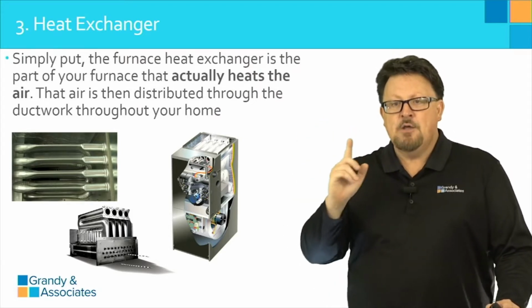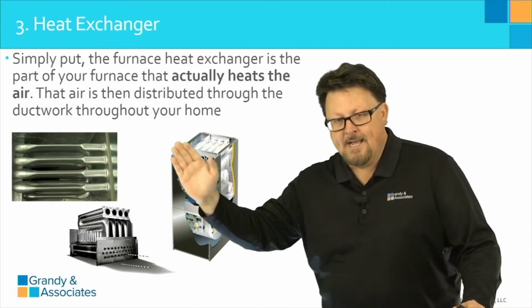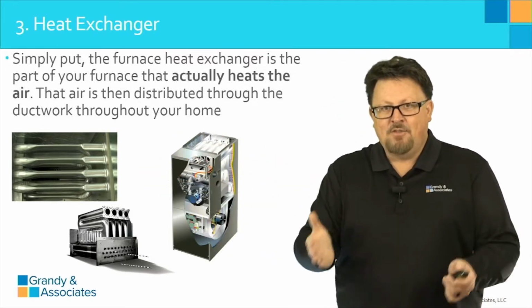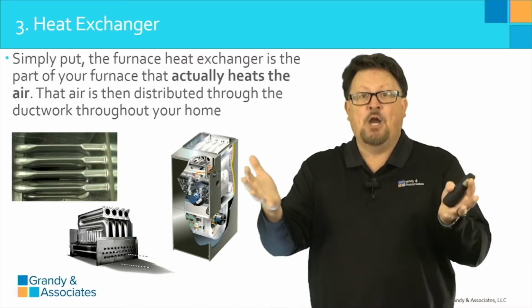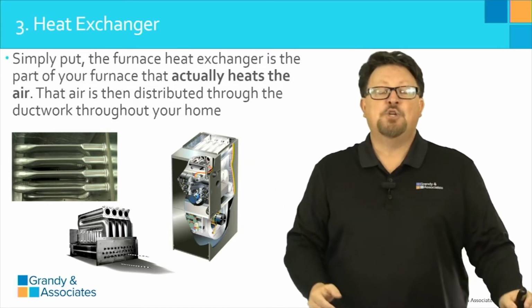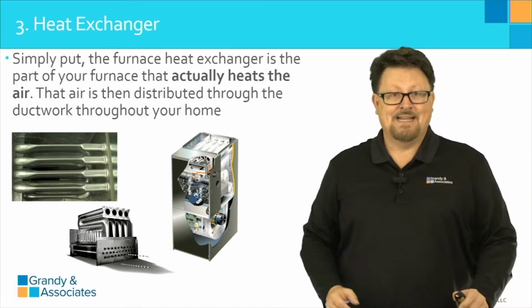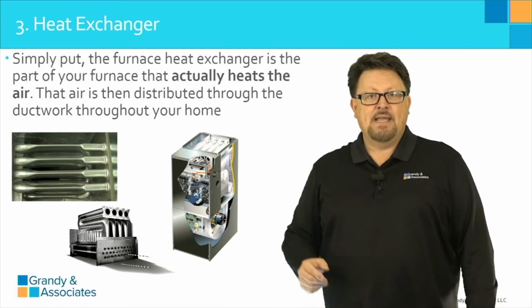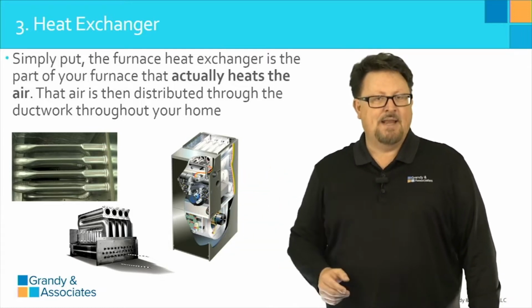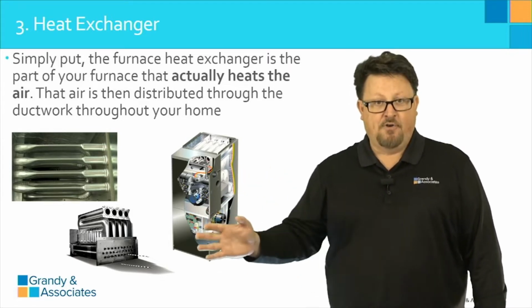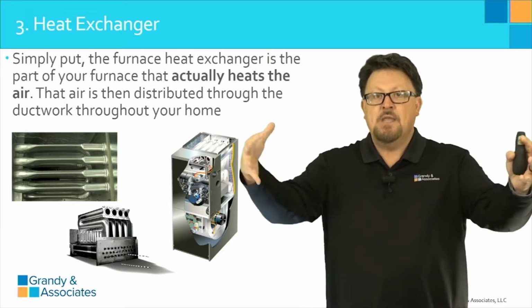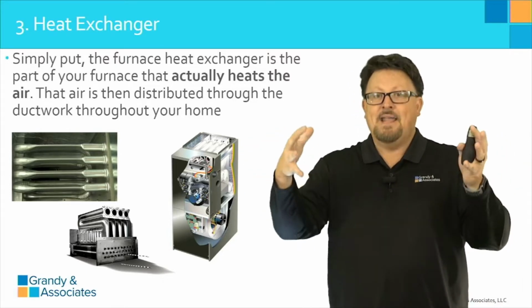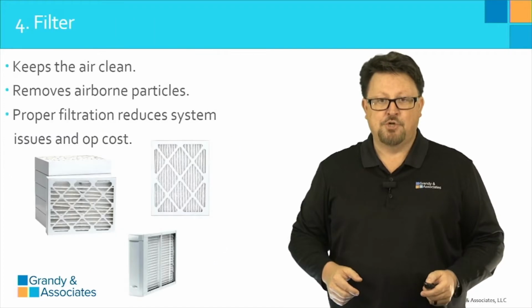And it is very important for this area to be balanced. In other words, we want it hot to heat the air, but not too hot so that it leads to cracks. A cracked heat exchanger is one of the most costly and expensive repairs to the furnace. So keeping that area properly vented is a premium for sure.